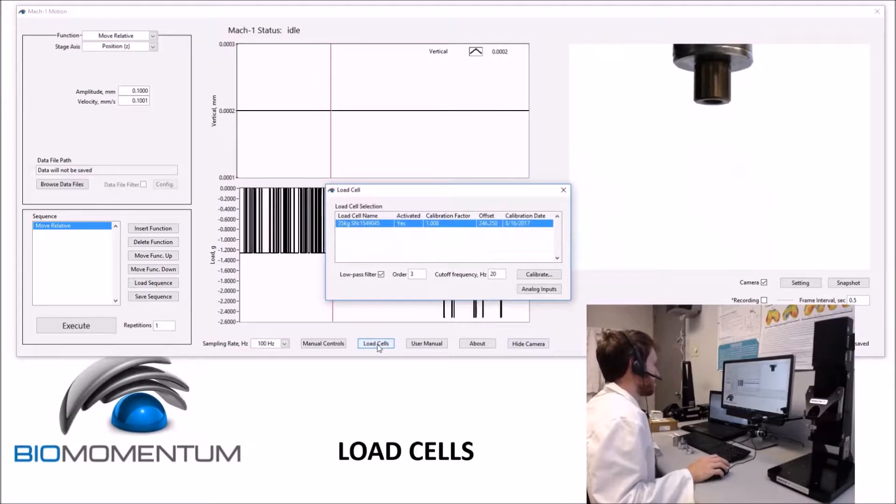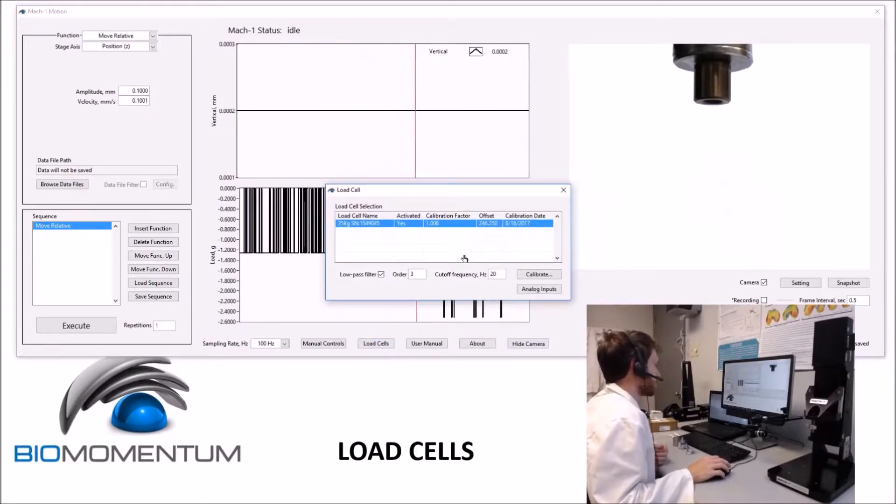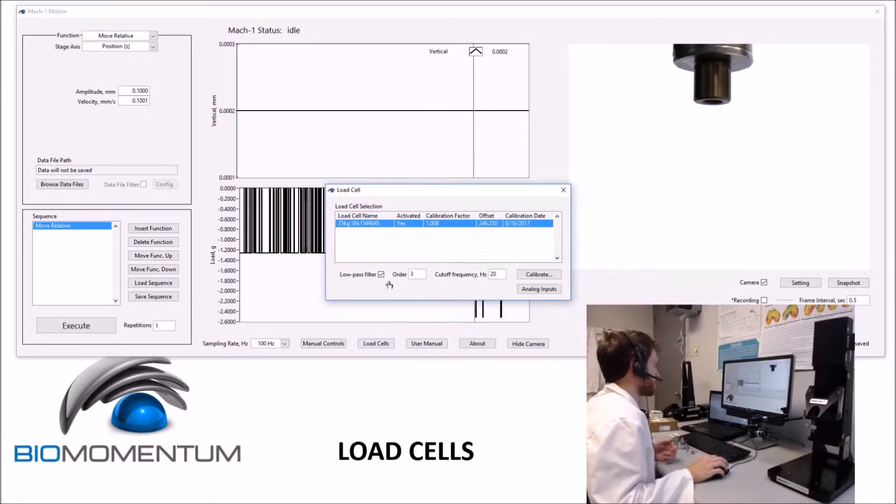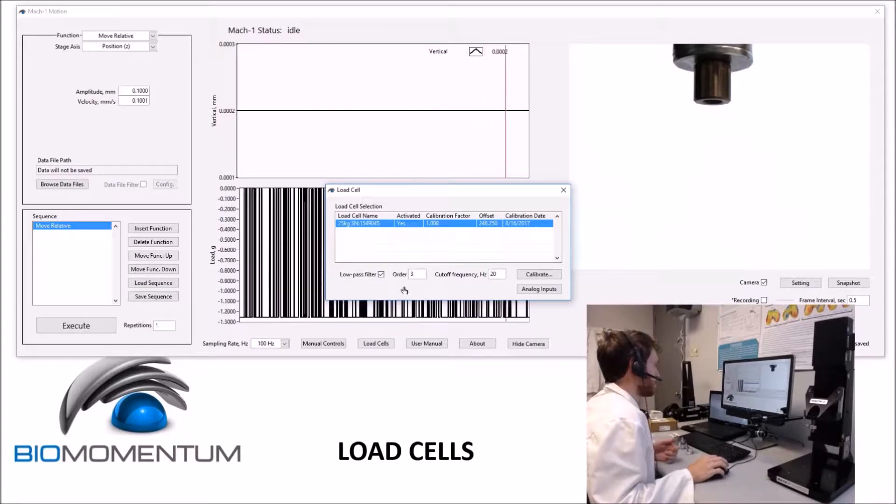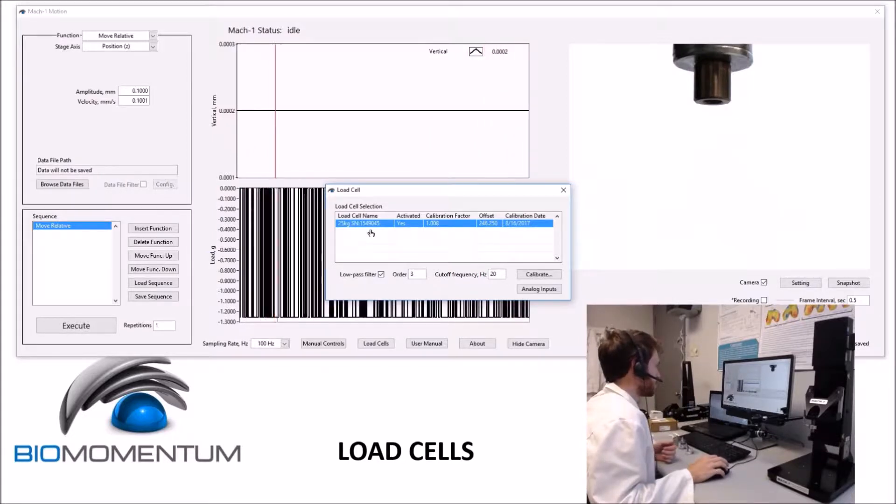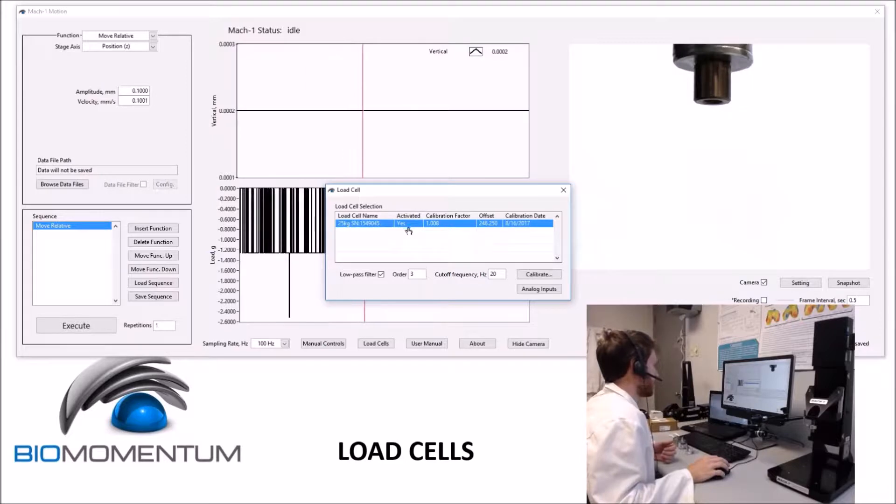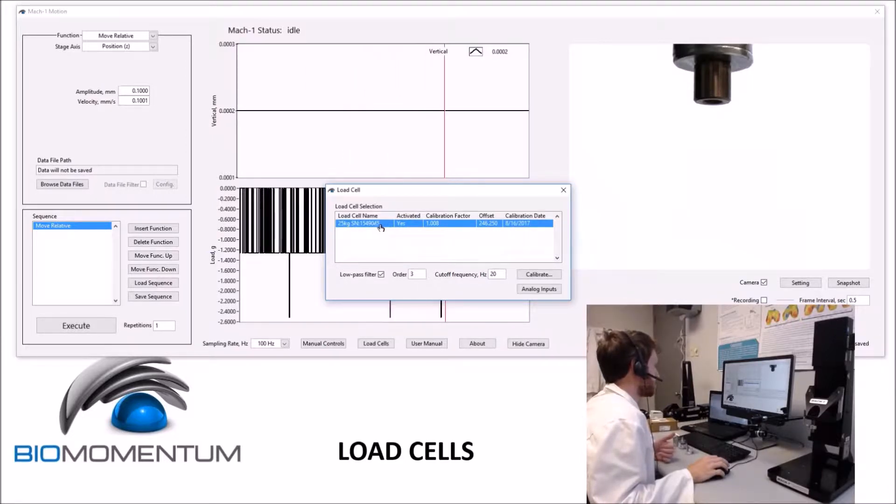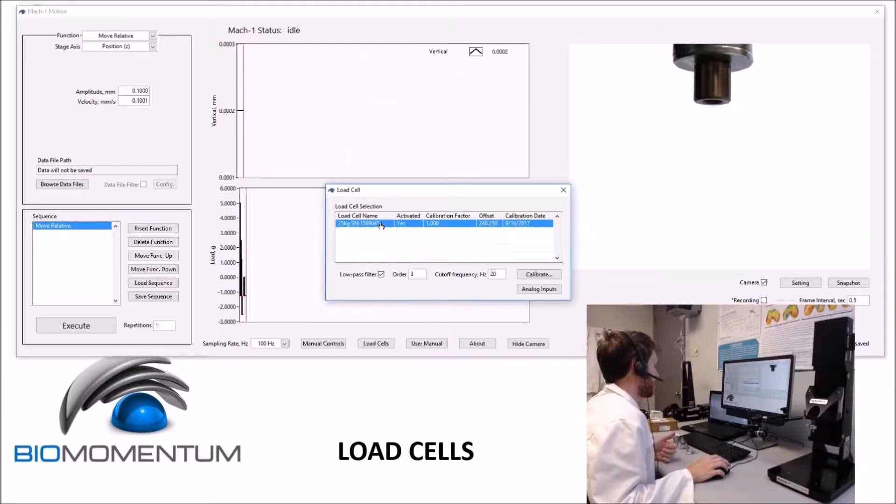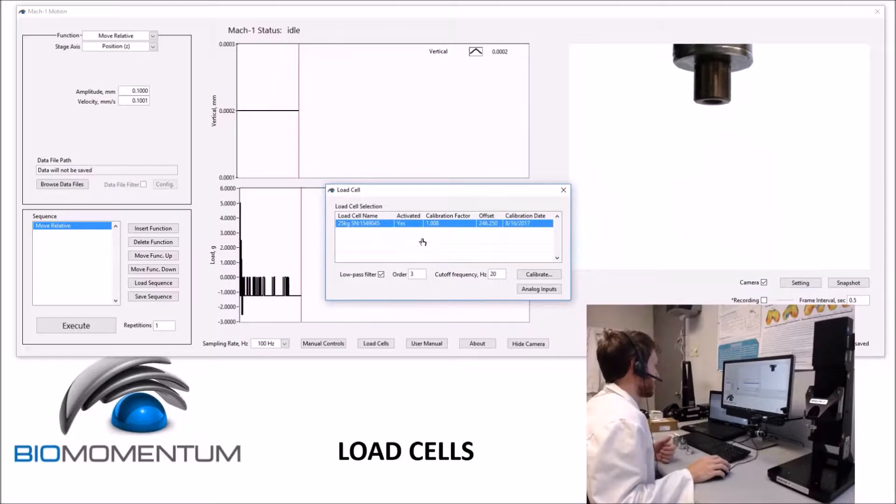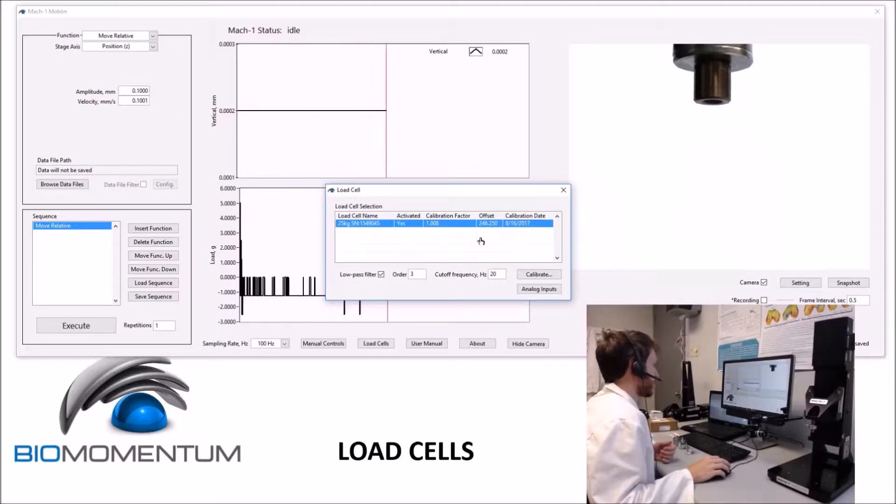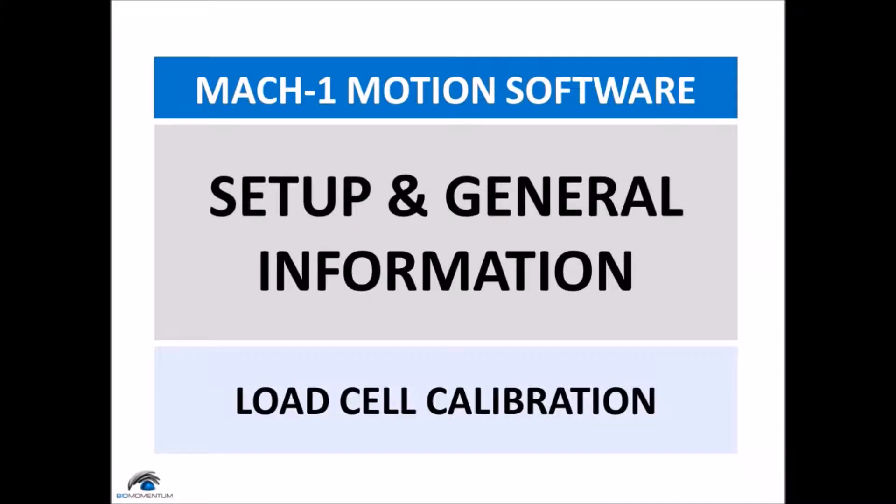Clicking the Load Cell button will open a window that allows the selection and calibration of a load cell, as well as the selection of a low-pass filter to reduce the noise in the load signal. All the available load cells will be listed, and the Activated column will indicate which load cell is activated. Double-clicking any load cell will activate it, and only one can be activated at a time. The other three columns are produced automatically after a calibration procedure.